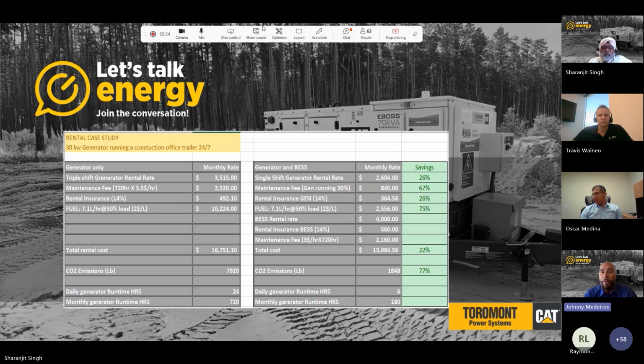That translates also to the maintenance fees. If you're running the generator 720 hours during the month versus only 180 hours, you'd have a 67% savings on maintenance fees. We also, like any other rental company, have insurance, which is 14% of the rental rate. So with the rental rate being lower because the generator runs less, you'd save 26% there as well.